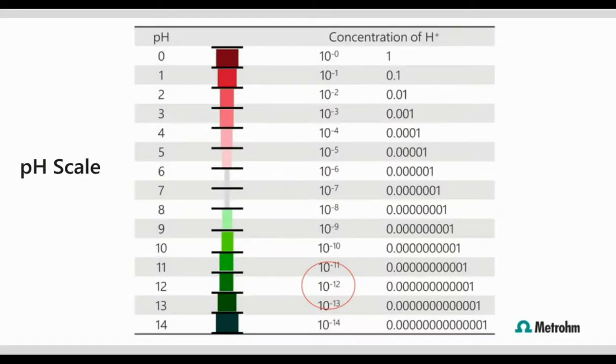Okay, so if we keep moving here by taking a look at the pH scale and really consider for a moment what we're asking of these electrodes. You'll see on the left the standard pH scale that ranges from 0 to 14. On the right, you'll see what pH measurement means in terms of the concentration of H+ ions. You'll notice at very high pHs, there are very few H+ ions in the solution. Basically, this becomes a very difficult range to measure pH in, since our pH electrode, you should basically think of it as an ion-sensitive electrode for H+ ions.